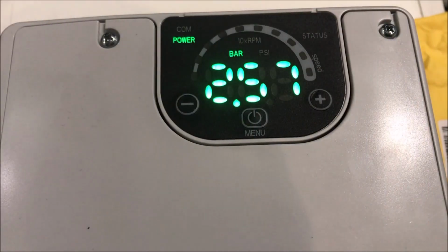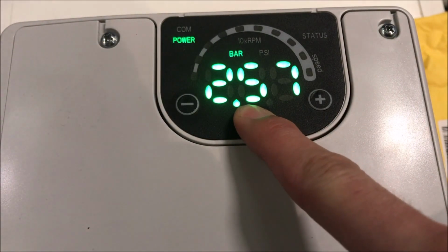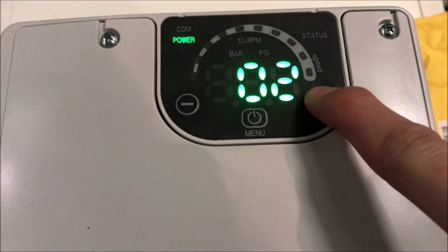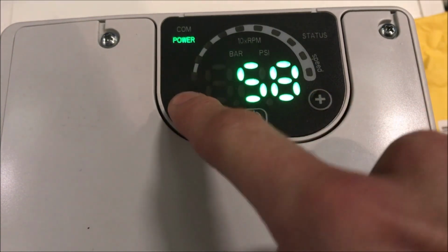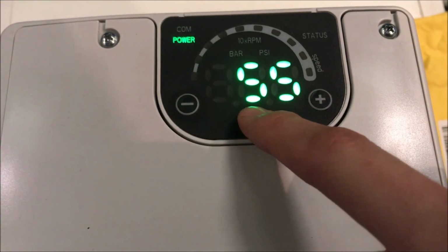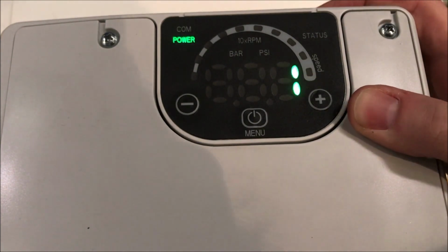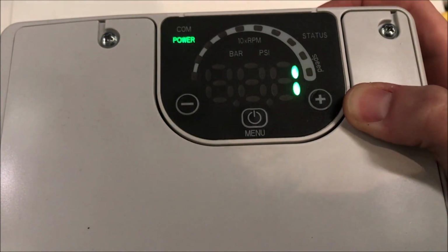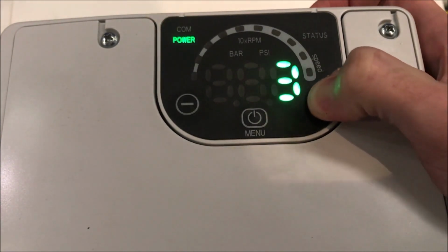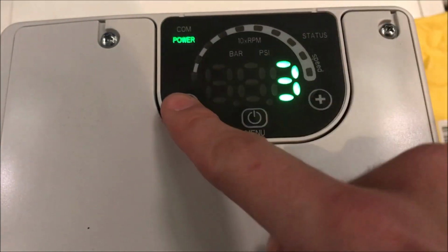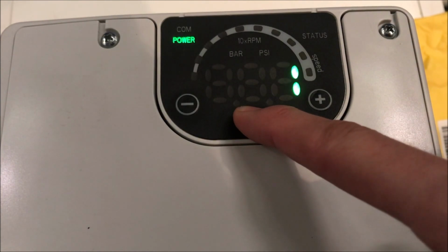When running the device in multiple pump mode, you will need to assign each pump an individual address. To do this, navigate to parameter 55. You can then change the address of the device between 1, 2, and 3. You need to carry out the same process on all other drives on the twin or 3 pump set. Each pump will need to have a unique address.